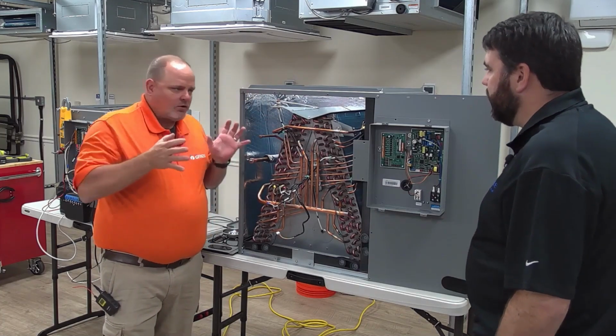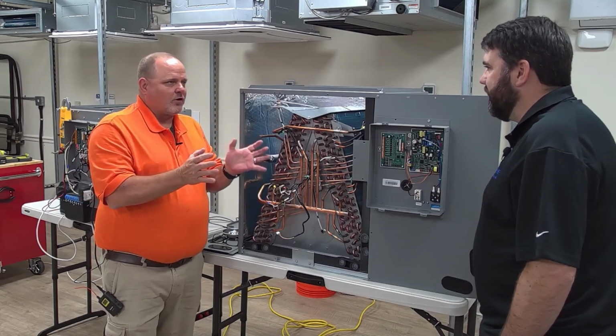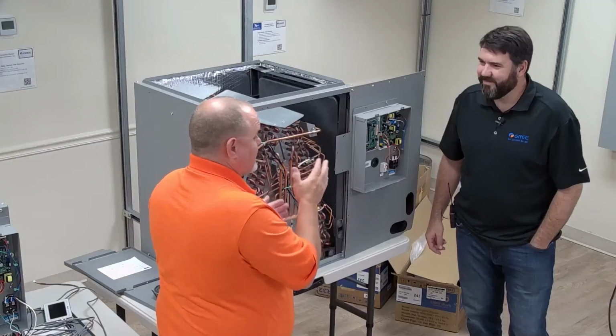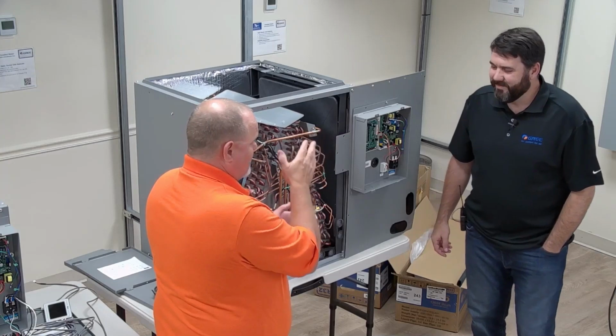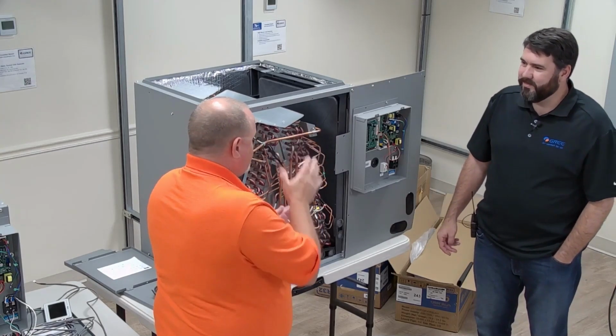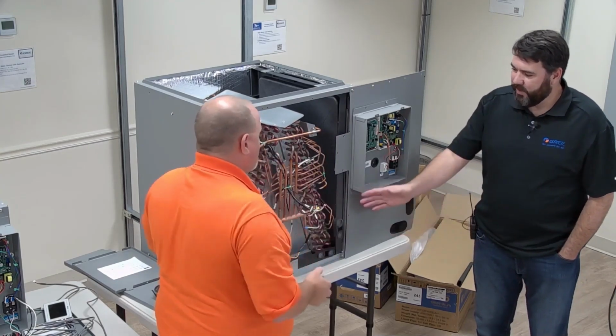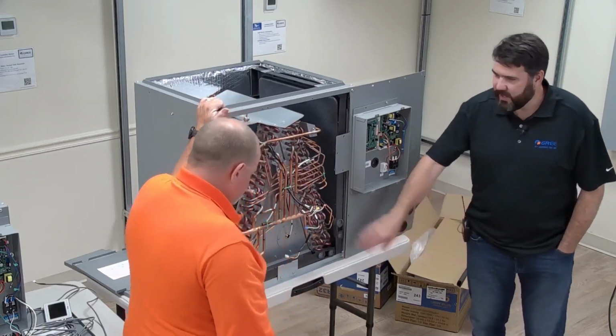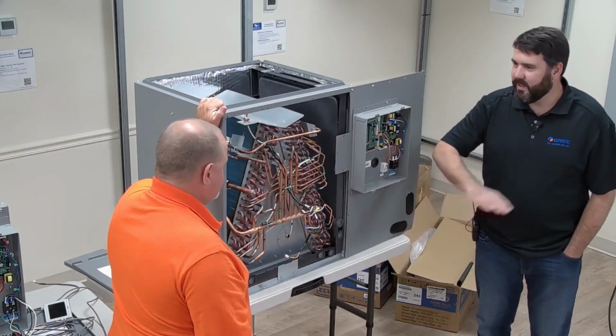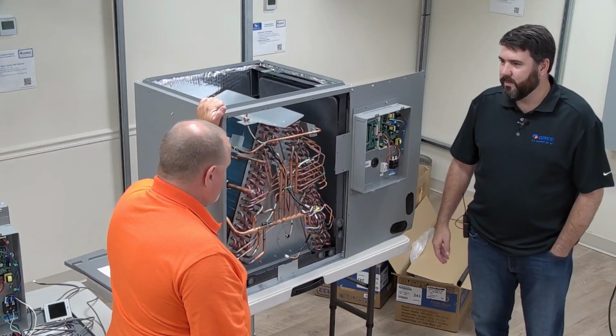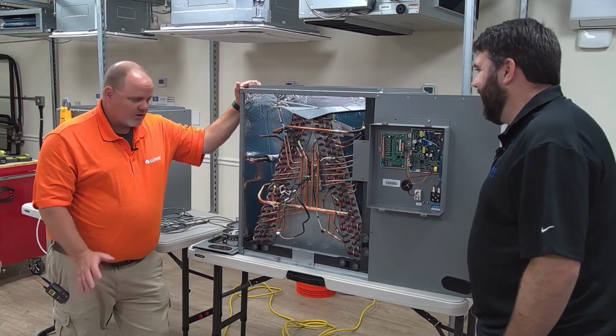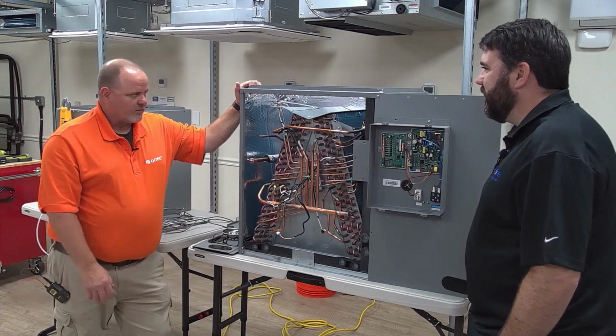Mm-hmm. And then when you go to try to shove the coil in there, it don't want to go in there because the case is racked, and it may not even be evident to your eye. Yep. It could just be racked enough that you're like, why ain't this thing going in here? If you've already attached it, taped it, mastic, all of that, then you got a big issue. Yeah, you're not going to be happy. So you're much better off to do this ahead of time.